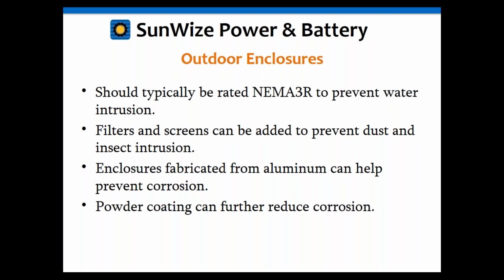You can add filters and screens to prevent dust and insects from getting in through open louvers. If bugs or dust blowing in is an issue at your location, you can add screens, just using window screen material tacked up there, along with filter material to keep dust out. It can be pretty simple—often you can just take it out as part of maintenance, rinse it off or clean it, and put it right back in.